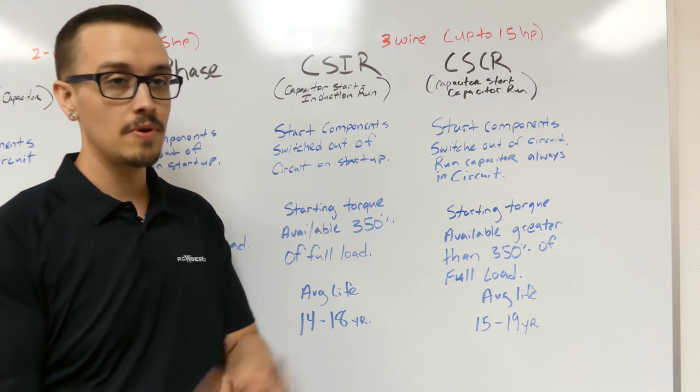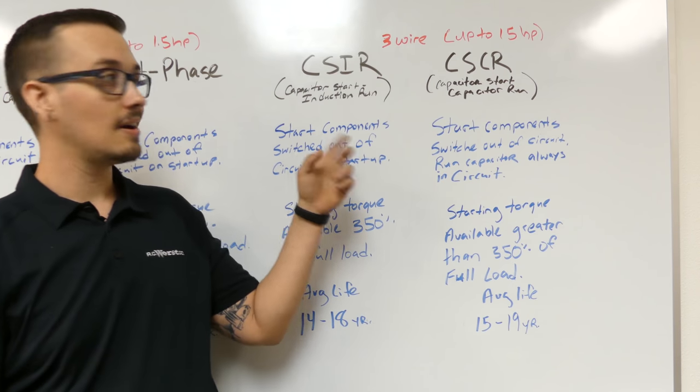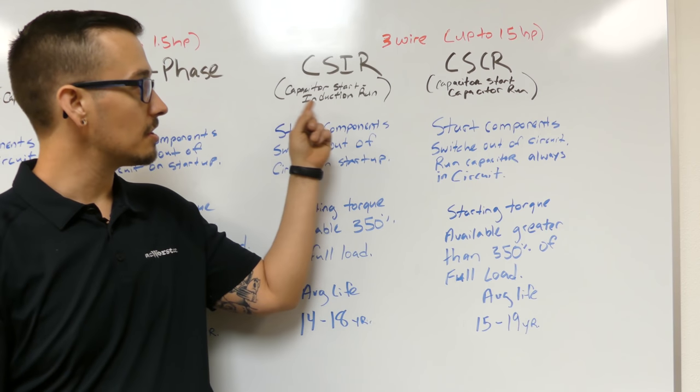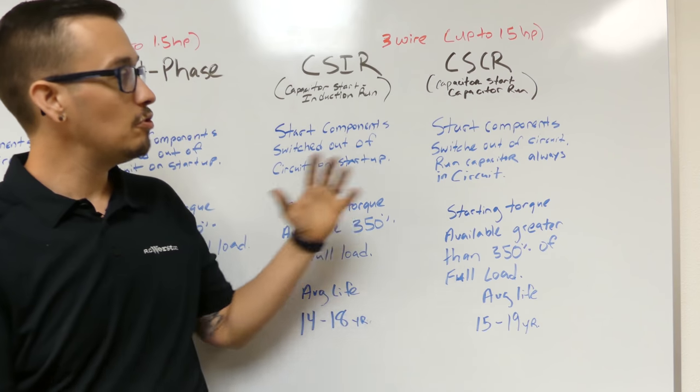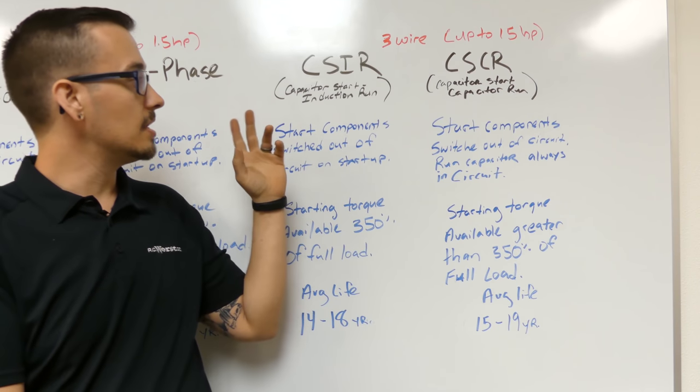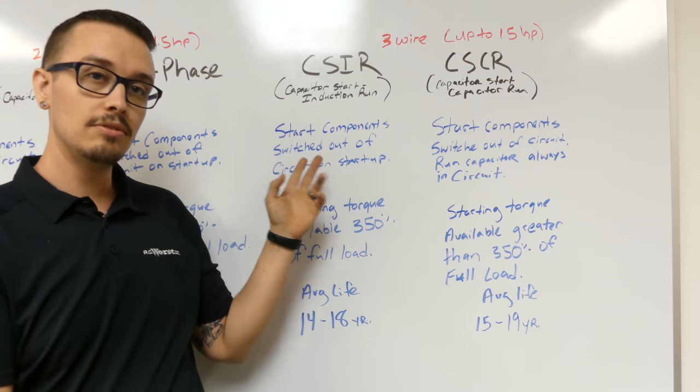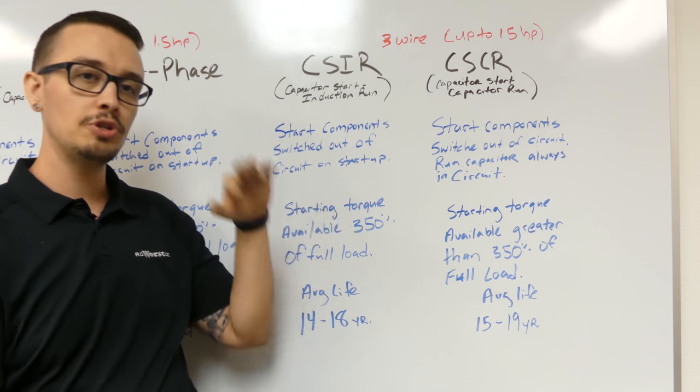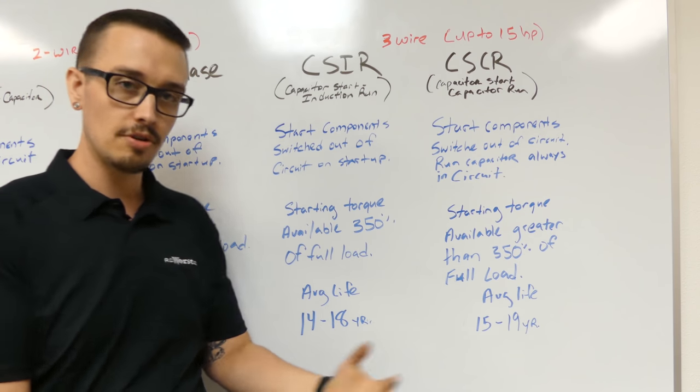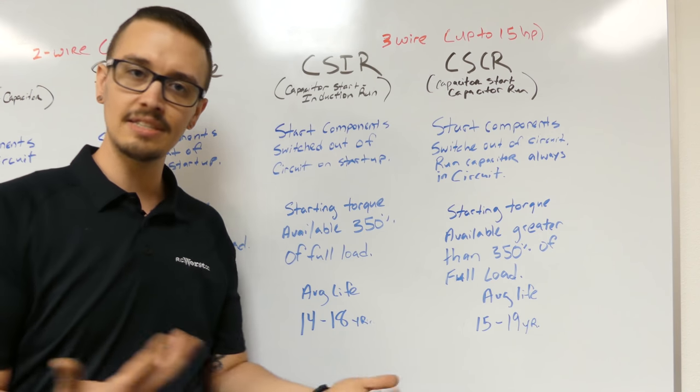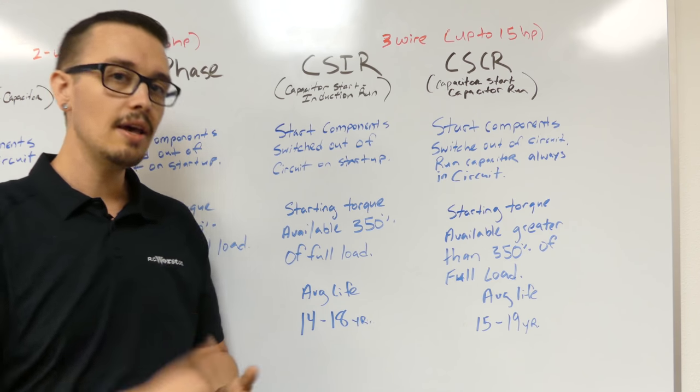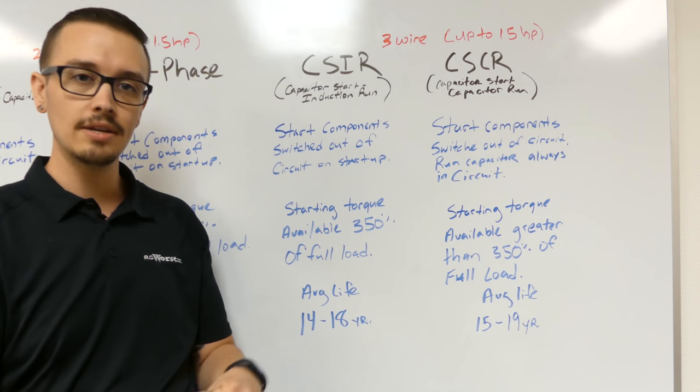All right, so here we are with the three wire motors. Again, we've got the CSIR, which is Capacitor Start Induction Run, or the CSCR, Capacitor Start Capacitor Run. Two big differences between these is on the CSIR panels, the starting components actually switch out of the circuit once the startup process is complete. Basically, once the motor gets up to roughly 70-75% of speed, the starting components and the winding is going to disengage.